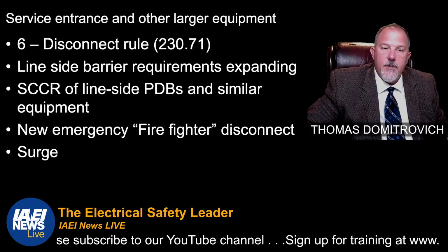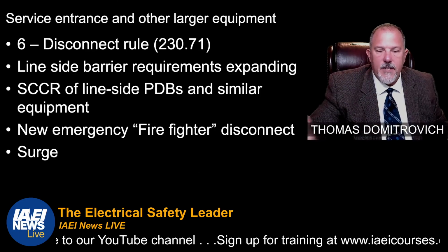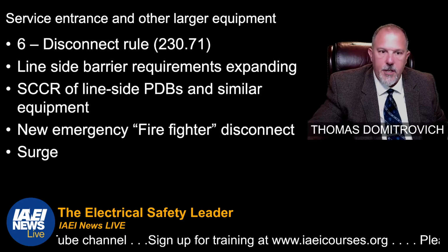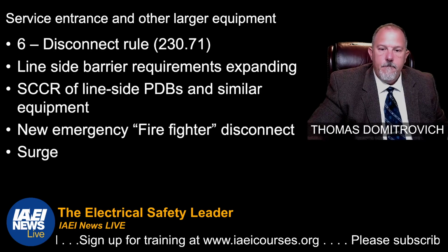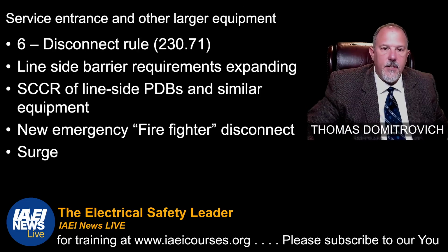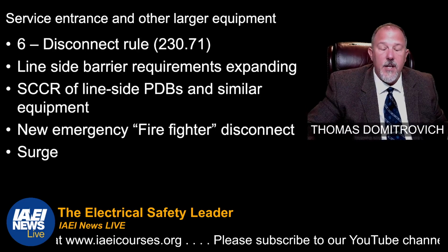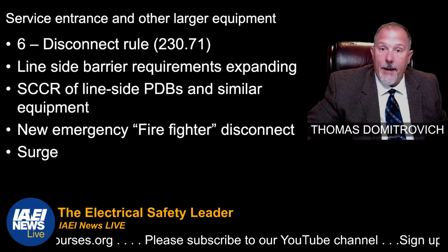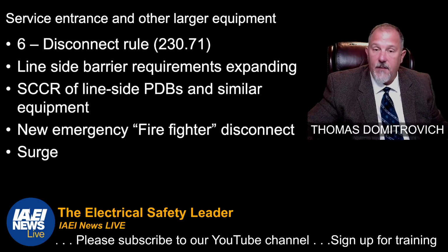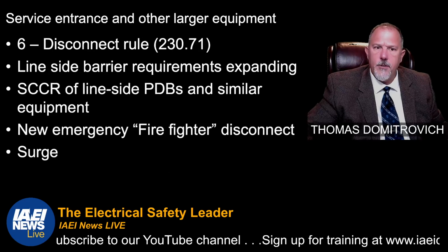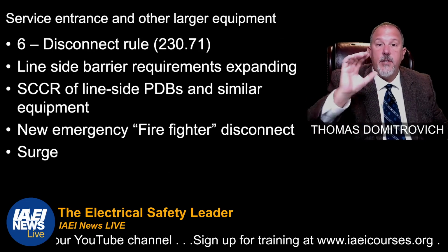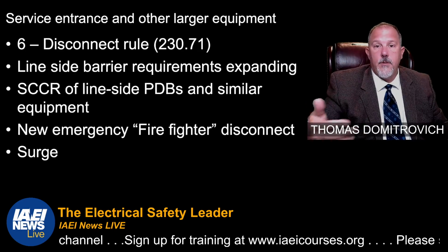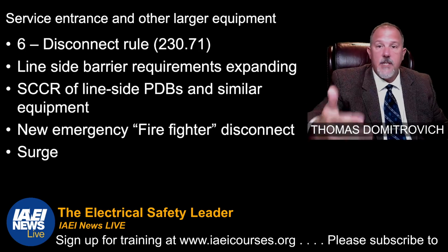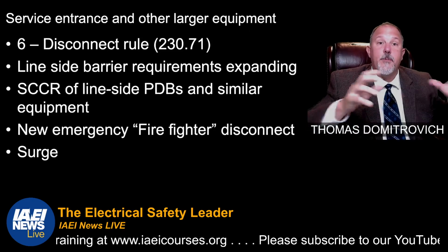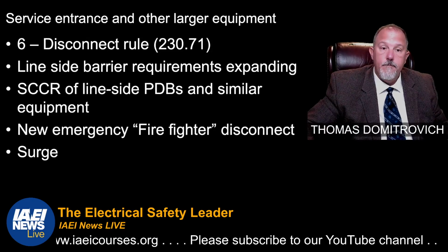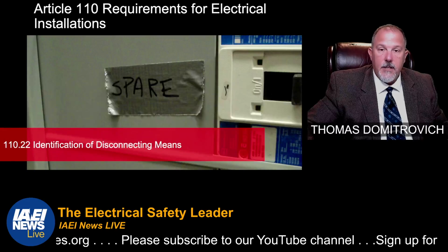Line side barrier. They expanded it to much more than just panel boards, switchboards, and switchgear. These are just the different things that you're going to see. In surge, some panel boards, the challenge with surge is how do you add it if you don't have any additional spots. So some manufacturers, I think pretty much every manufacturer of breakers, will have integrated surge where you can take, say, a 30 amp or a 60 amp circuit breaker out, put a 60 amp breaker back in again, and it has surge that protects the entire panel and connected loads.